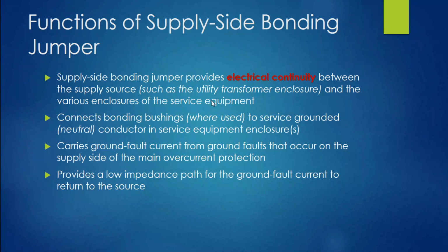Okay, so all of that gets tied together, providing electrical continuity between them all. Theoretically here, we're bonding it all together. It connects bonding bushings where used, because you might have bonding locknuts, if we'll show you where they're adequate, to service grounded neutral conductors in the service equipment enclosures. Again, that's the jumpers that we're going to talk about, which tie all of them.